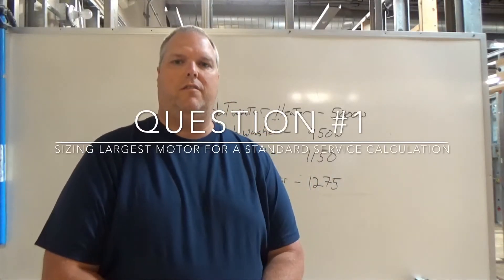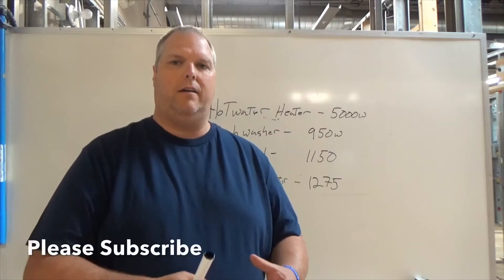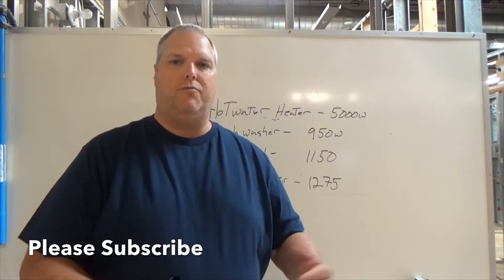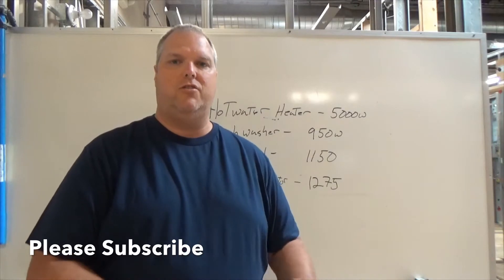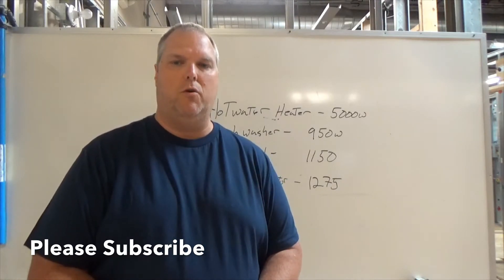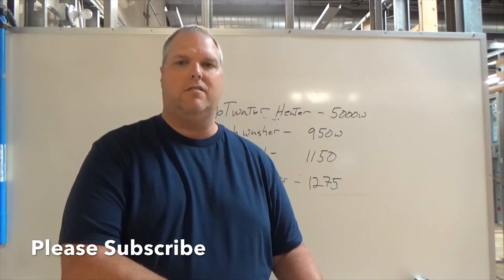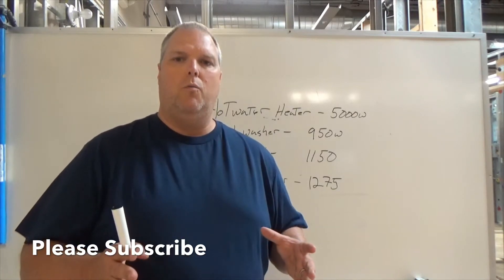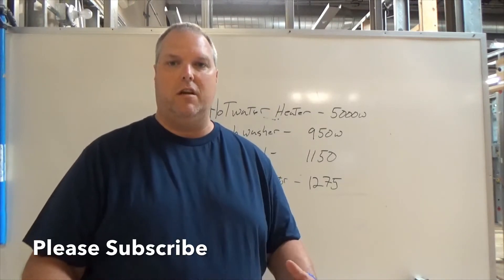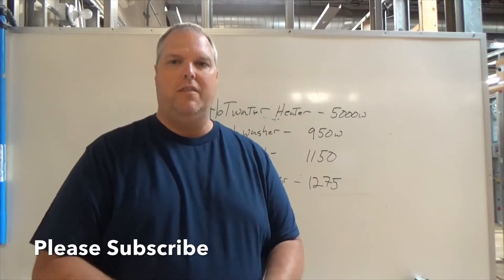The first part of the question is sizing the largest motor. We have to go back and think about the standard calculation. In the standard calculation we size the general lighting load, then we size fixed appliances. In the fixed appliances that's where we'll most likely find our largest motor, unless we have air conditioning that becomes larger. The whole point today is just sizing the largest motor, which is line 14 — how do we come up with that percentage?